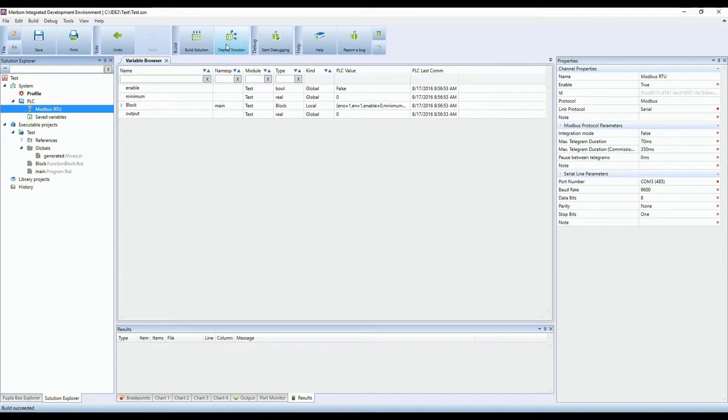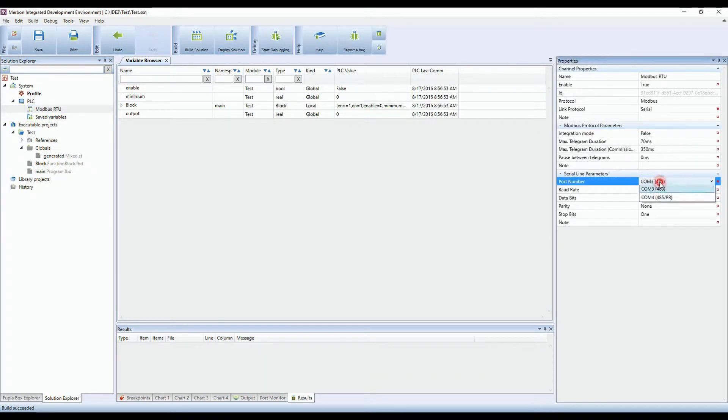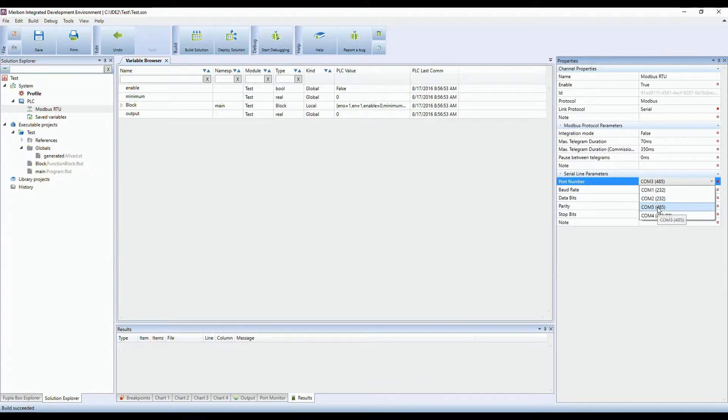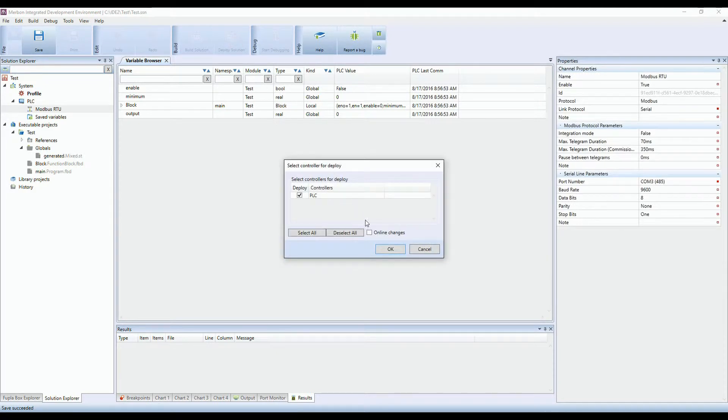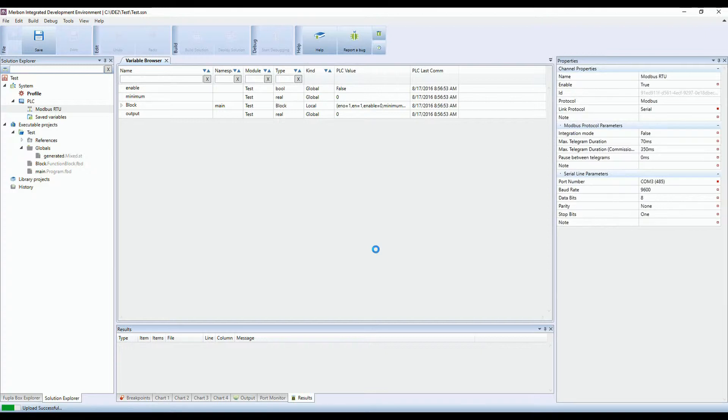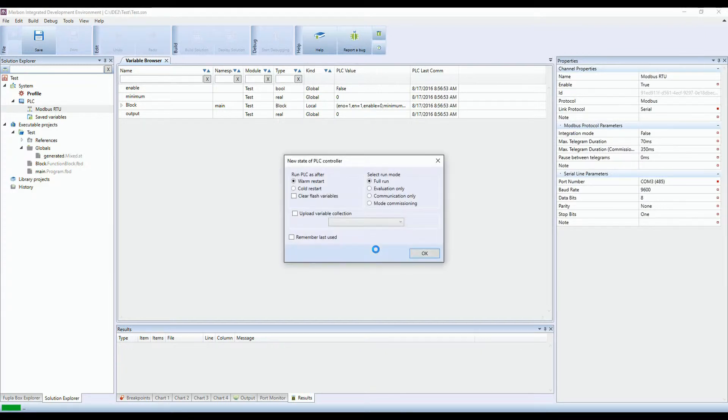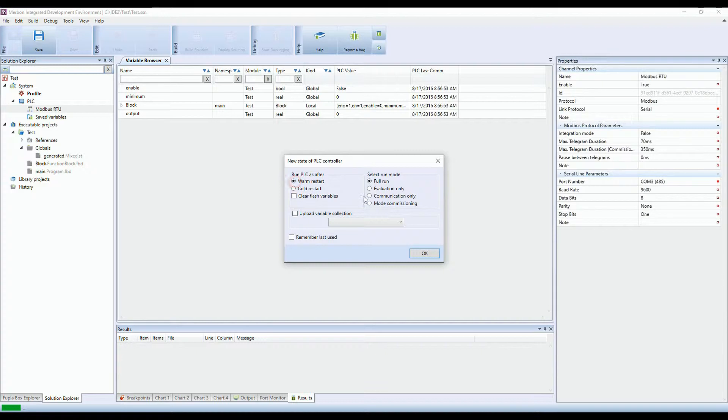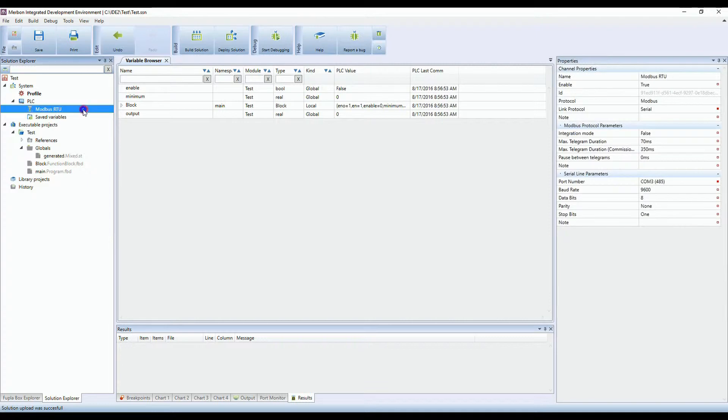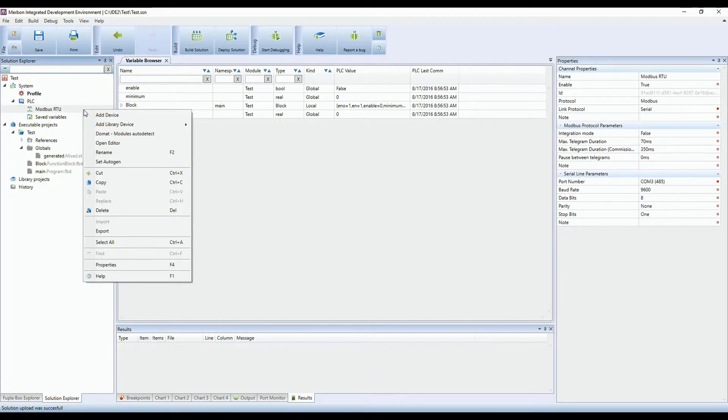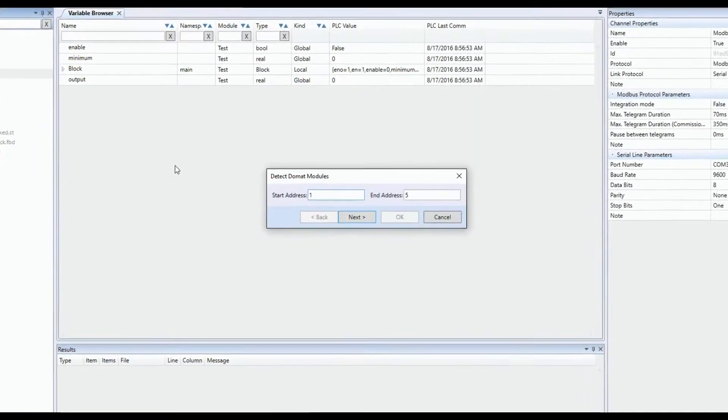Check the channel setup and deploy the solution to the PLC. Choose the commissioning mode as a run mode for PLC. The PLC will act as some sort of converter and you'll be able to communicate with the devices on its bus. Click on channel and choose DOMAT module autodetect and choose the range of addresses.